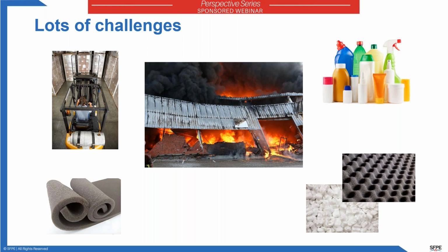So you could have things that would be considered somewhat innocuous, like class 1 commodity, which is essentially things that don't burn, which unfortunately you don't find too many warehouses that are just class 1 commodity. And then as you increase along the hazard classification, you start to increase the amount of combustible material. So as you go from class 1 to say class 3, you start to increase the amount of plastics that get involved, to the point that you jump from the class 1, 2, 3, 4 all the way to group A plastics. And then the plastics themselves offer a tremendous amount of challenges to an effective fire sprinkler system due to the heat release rate that's generated.